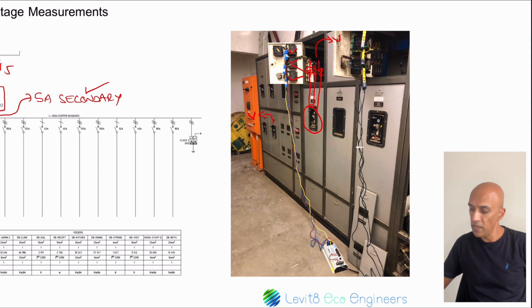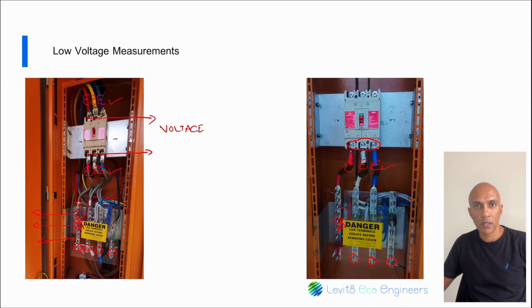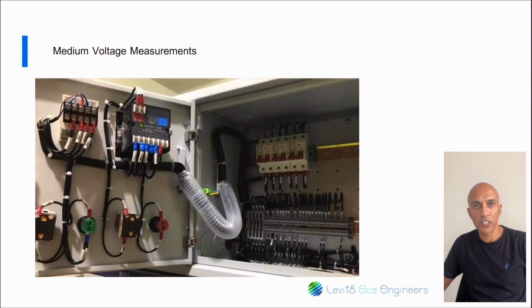Now, when we come to medium voltage measurements, it is quite different. For medium voltage equipment, one cannot simply connect the voltage leads to 11 kV points or place current clamps around medium voltage phase cables for obvious safety reasons. That is why medium voltage cables are inaccessible. Here is a typical 11 kV protection panel.